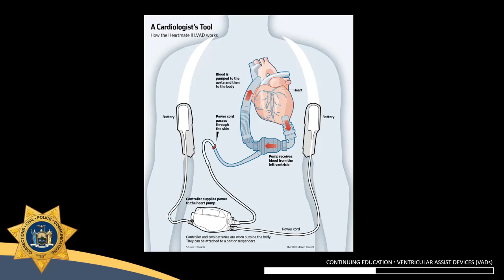And it leads to a control pack. The controller is usually worn in a fanny pack or on their belt or things like that. And this particular picture also has the more modern style of battery pack where it's worn under the arms. And typically there are 2 batteries. The device is designed to run on one battery. The second battery is just a backup. It also lets you switch out the batteries. You switch out battery A, so the device uses battery B temporarily while you switch out battery A. But the patient has to be on battery power at all times.